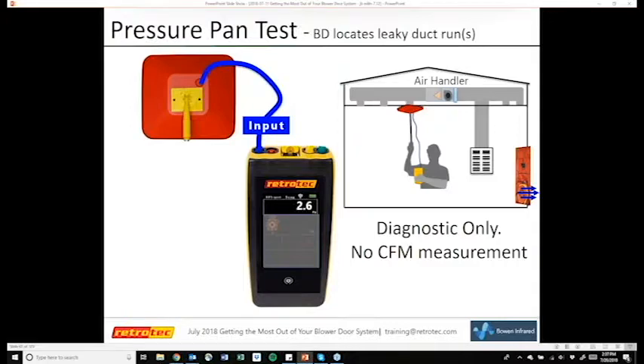Retrotec makes two different sizes of pressure pan. There's a smaller one that'll fit over most supplies, and a much larger one that'll fit over some return boxes. So if you run your duct tester and do a duct test and see that there is leakage, this is a way to pinpoint which branch it's coming from, or whether it's supply or return.